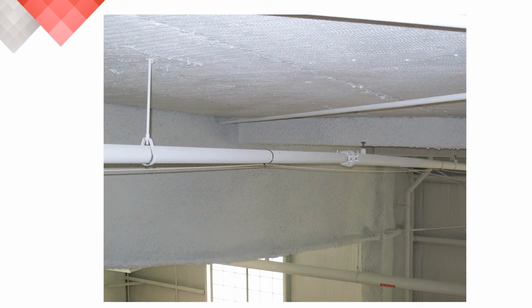On the screen in front of you, both the ceiling and sprinkler pipes have been painted. In accordance with our third-party approvals, the 190 Fahrenheit or 88C detector, which has a white outer jacket, was installed after everything else was painted. You cannot paint Protectowire.